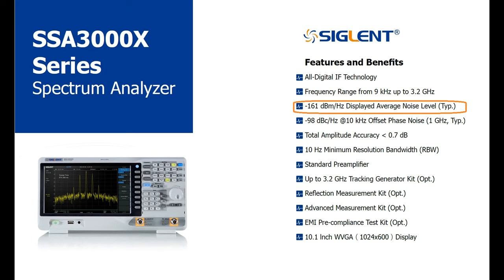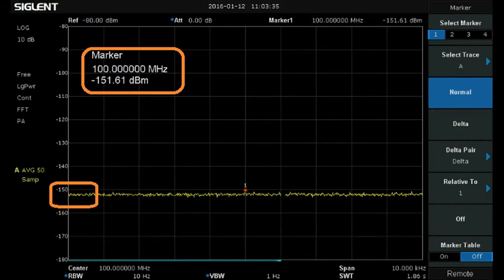DANL stands for displayed average noise level and it indicates the noise floor of the instrument. Lower noise floor values enable you to observe lower power signals. This is especially important when you are hunting for harmonics of a signal or potential interference sources. The SSA 3000X has a DANL of minus 161 dBm per hertz typical. The written spec is commonly normalized to 1Hz so the displayed noise floor of the instrument is typically near minus 151 dBm in actual use as we see here.